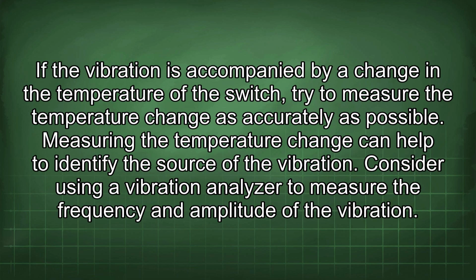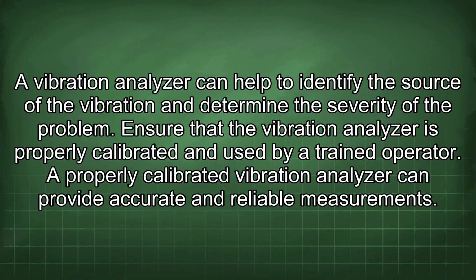Describing the change in sound can help to identify the source of the vibration. If the vibration is accompanied by a change in the temperature of the switch, try to measure the temperature change as accurately as possible. Measuring the temperature change can help to identify the source of the vibration. Consider using a vibration analyzer to measure the frequency and amplitude of the vibration. A vibration analyzer can help to identify the source of the vibration and determine the severity of the problem. Ensure that the vibration analyzer is properly calibrated and used by a trained operator. A properly calibrated vibration analyzer can provide accurate and reliable measurements.